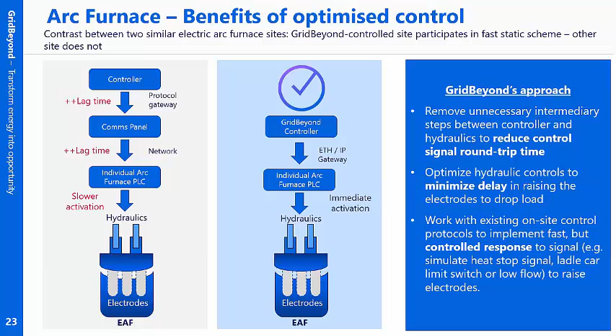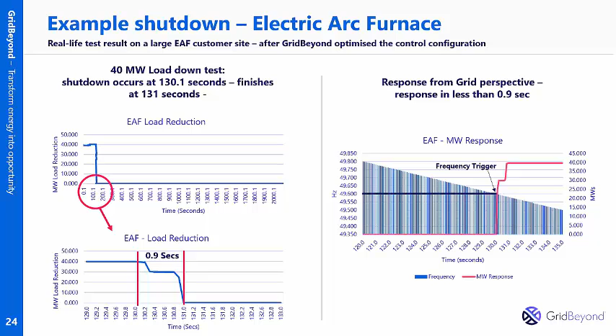Okay, so this is an example shutdown. This is data that we have gathered from Outokumpu's arc furnace. You can see it's 0.9 seconds. We have a piece of equipment that triggers a shutdown, but also monitors the shutdown as well. From that immediate trigger point, it starts counting, and it measures the load dropping in milliseconds. So as you can see, in 0.9 seconds, a 40 megawatt arc furnace drops its load using the control solution I've just discussed. If you want to go on again, Wayne.